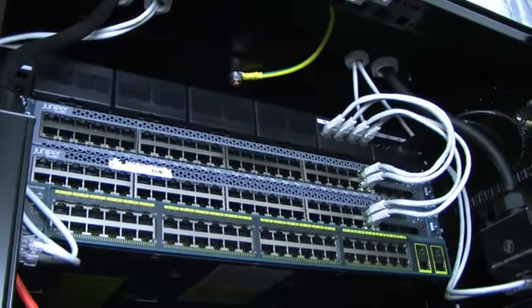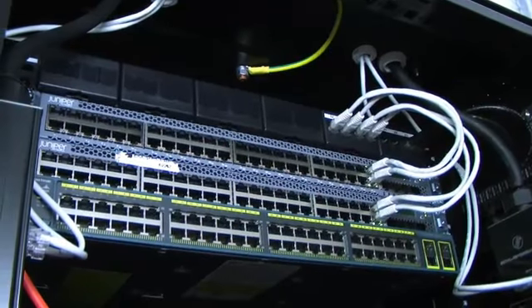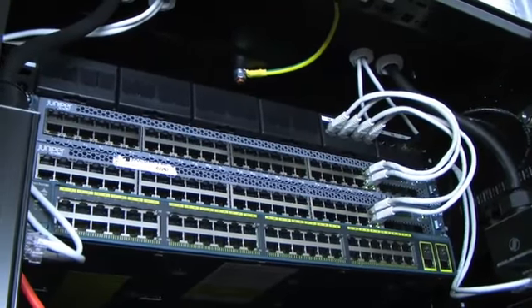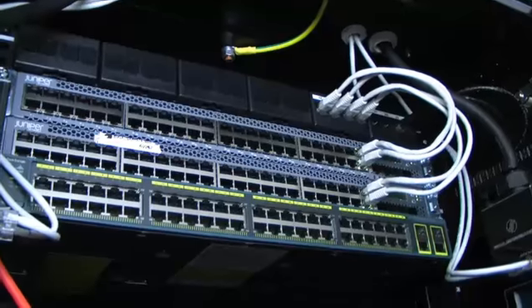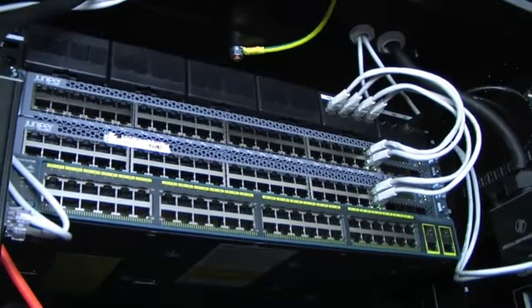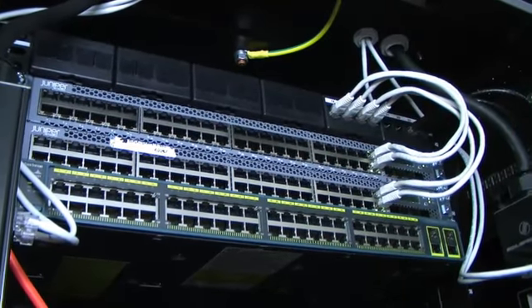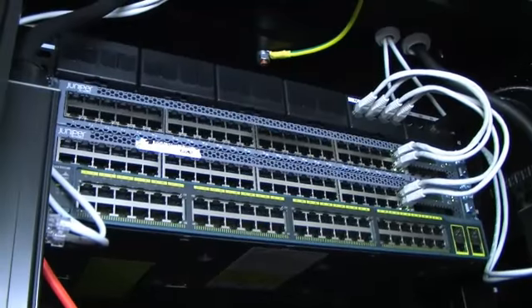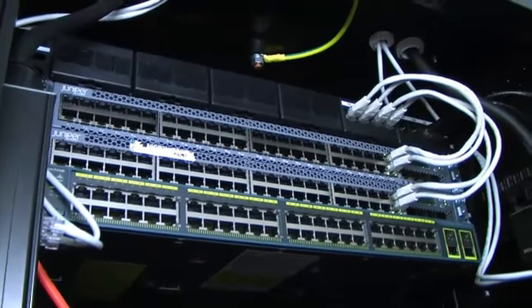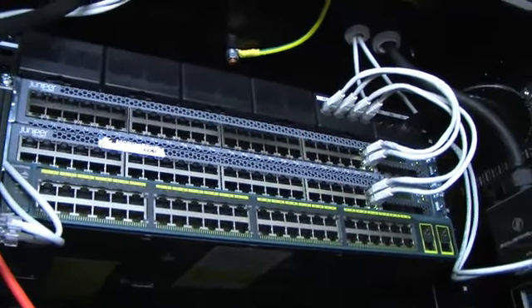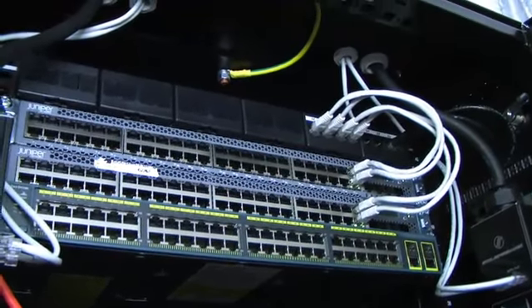Right. And because they're in the hot aisle, they need to take the cold air from somewhere to keep them optimum. Now, to be fair, that equipment's probably rated up to 34 degrees centigrade operational temperature anyway. But there's no point in driving it the opposite way to the way it's supposed to be. Exactly. Because what you end up with is loops of air within your cabinets, which is inefficient.